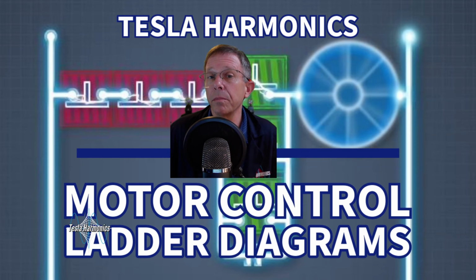And a lot of people ask, what is a master control relay? Well, the master control relay is a relay that serves as a central control point for the entire circuit. It's typically used to feed power to the control side of the circuit and is often controlled by a start-stop station. It can also have additional functions such as interlocking or providing status indications for equipment. The master control relay is an important component in ensuring safe and efficient operation in motor control circuits. All right, so let's take a look at that right now.